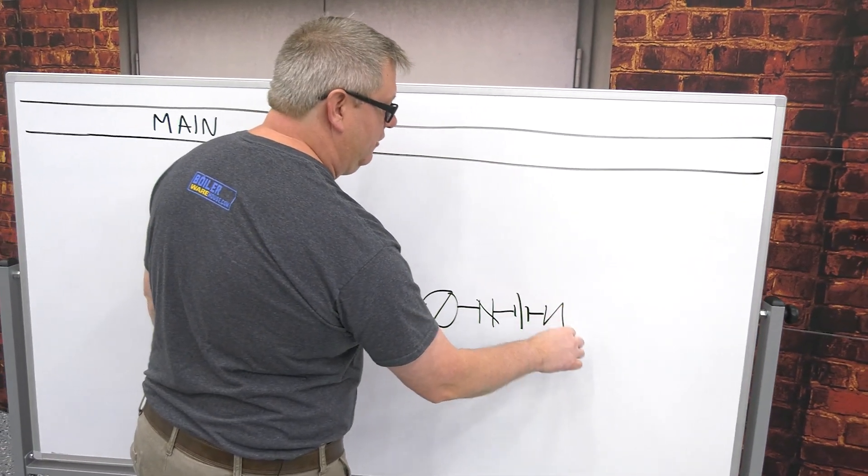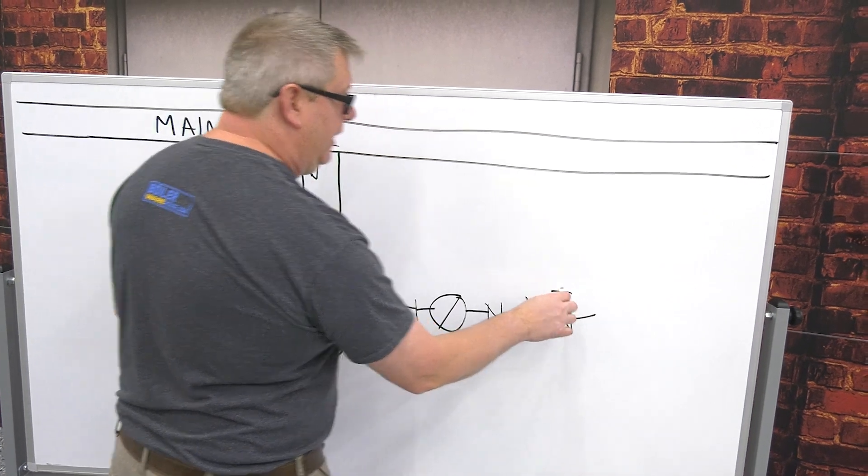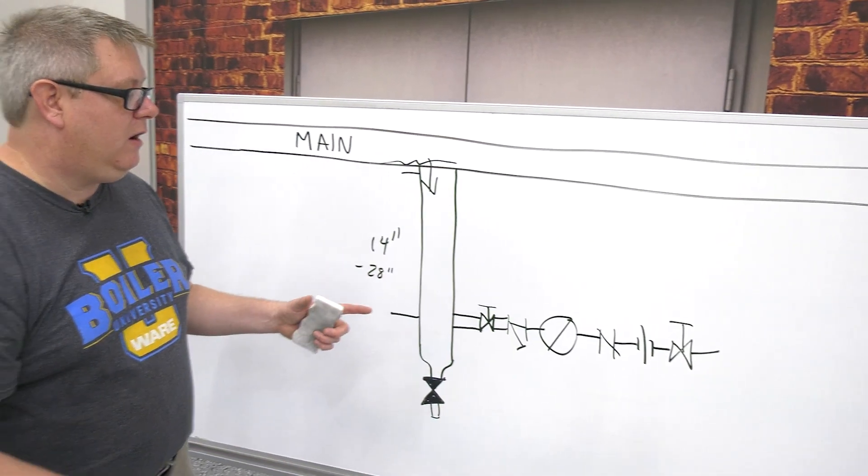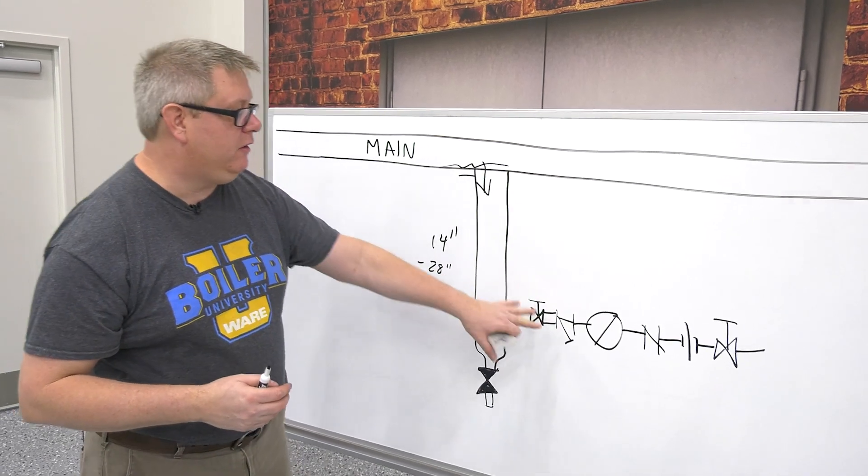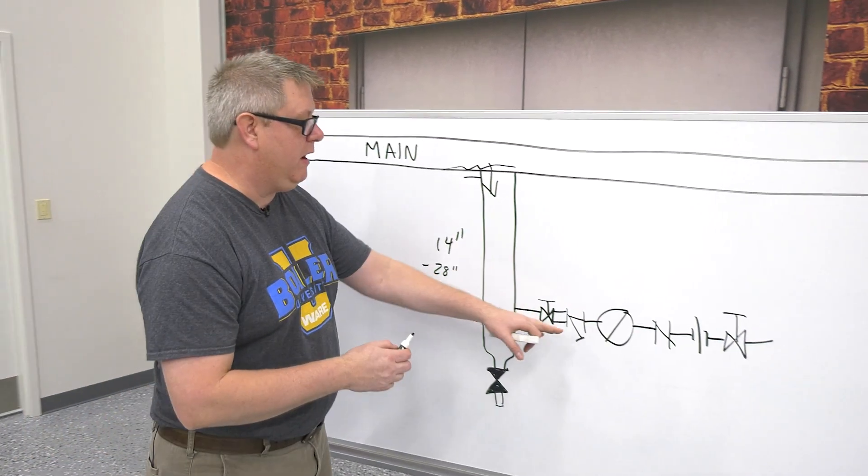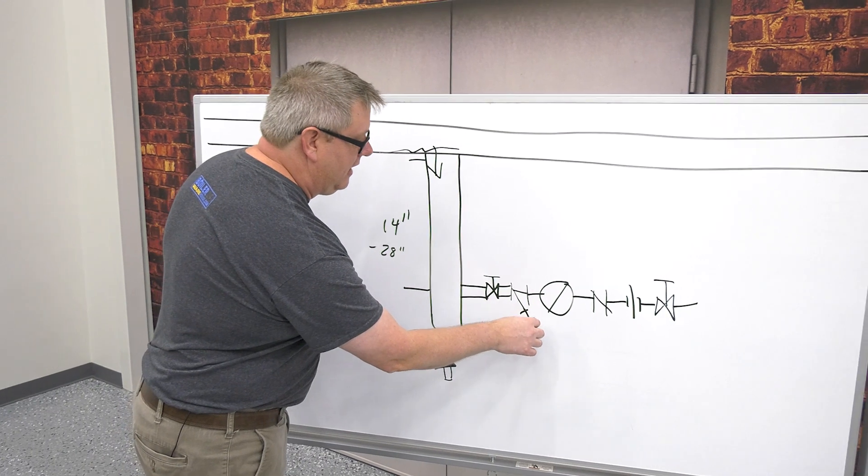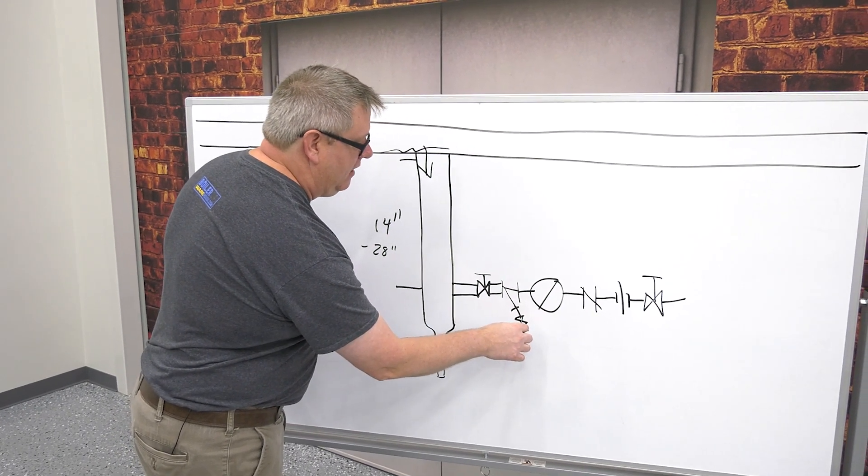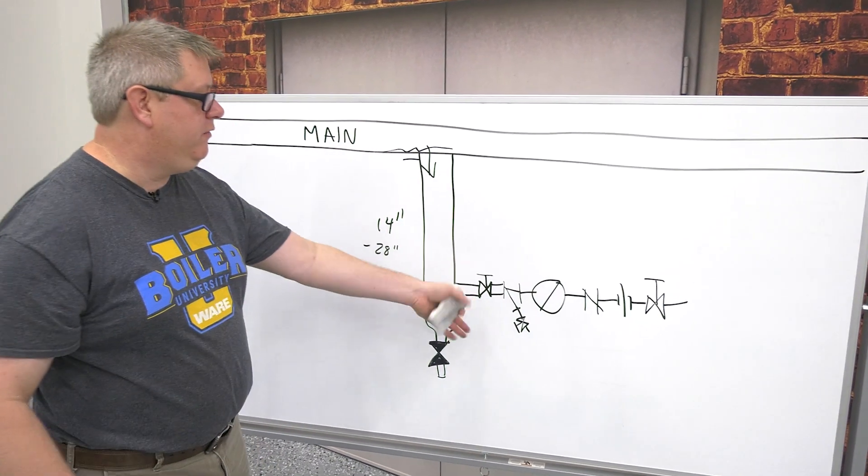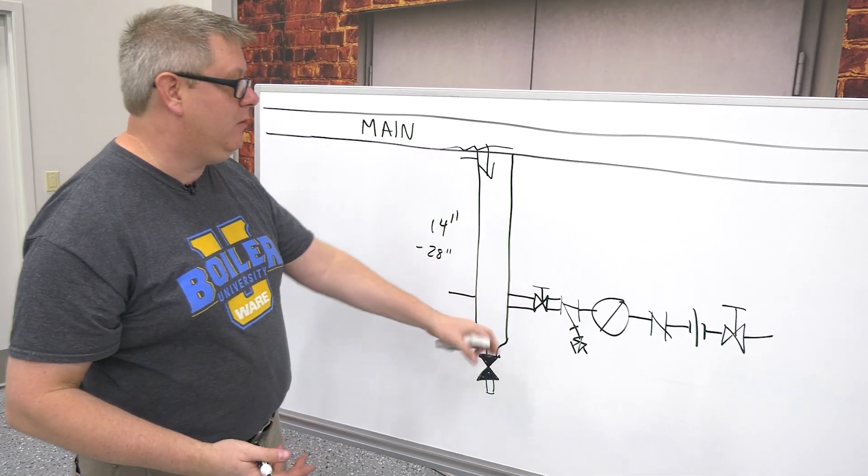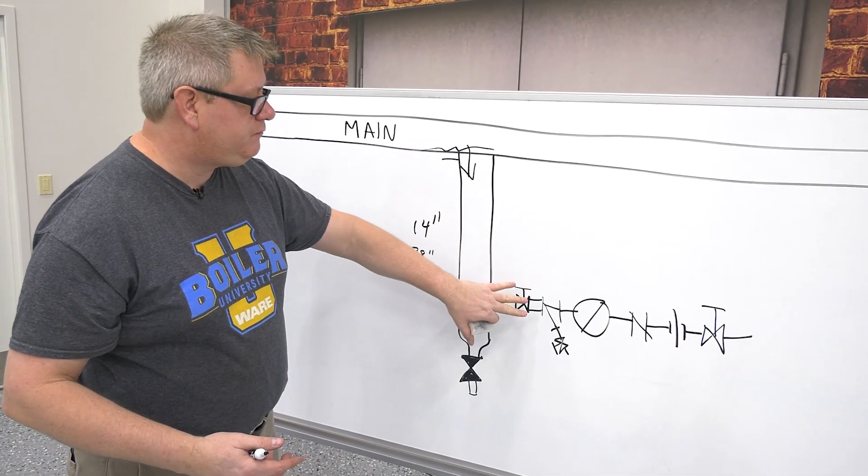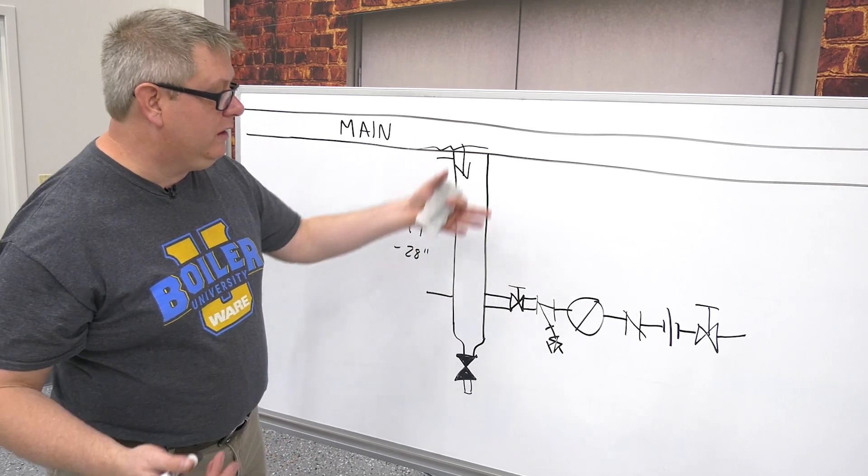And then we'll have another isolation valve. Now every plant's got different rules. We may not be able to blow down this strainer trusting that that valve works by removing the plug. So it's not a bad idea to put a valve on the outlet of the strainer. That way we can open that valve and not have to worry about this valve holding completely.